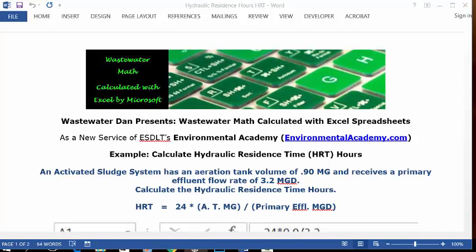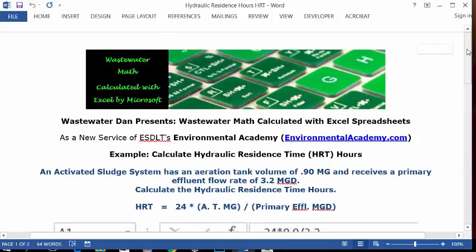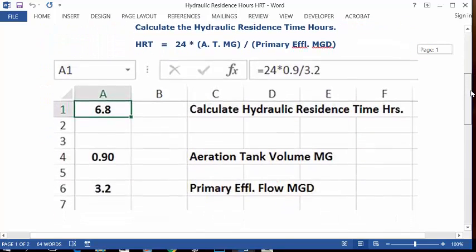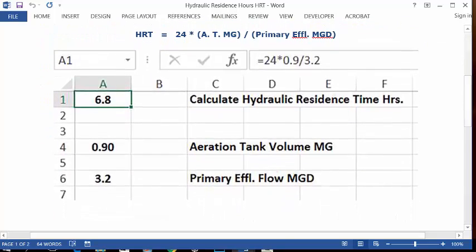This problem uses the formula: HRT equals 24 times aeration tank million gallons divided by primary effluent MGD, or million gallons per day. Let's let the Excel spreadsheet do the work for us and see how we can put this in Excel.